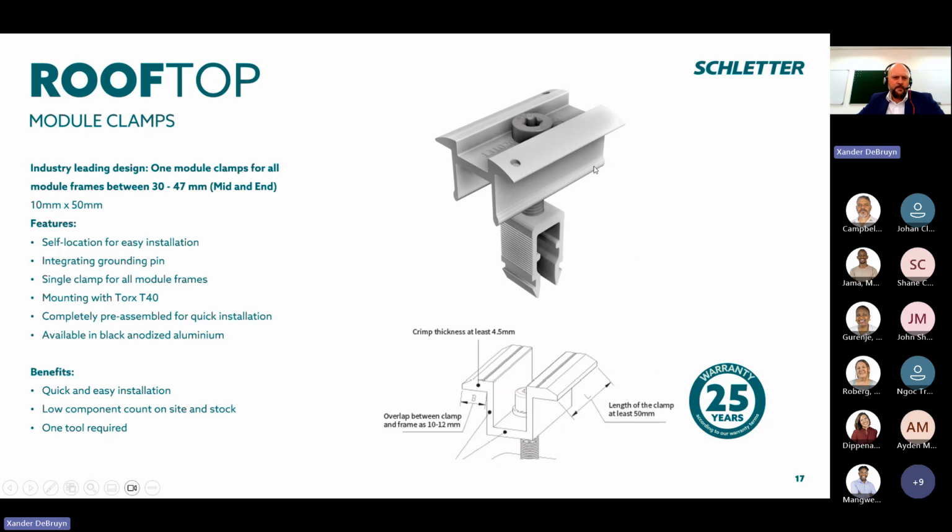It has a very, very fine integrated grounding and bonding pin, which is designed to penetrate through the anodizing on the PV module frame so that you don't have to bond every module to each other. It also causes little enough damage that it does not void the module warranties, which is an important part of any project.